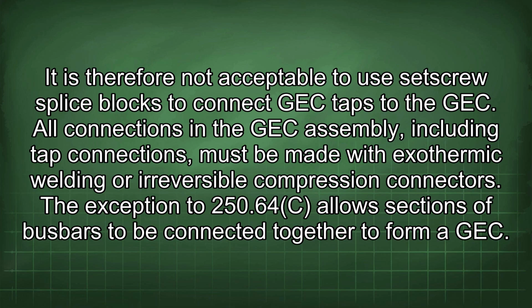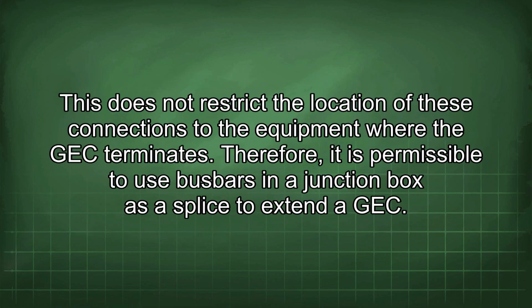All connections in the GEC assembly, including tap connections, must be made with exothermic welding or irreversible compression connectors. The exception to 250.64(C) allows sections of busbars to be connected together to form a GEC. This does not restrict the location of these connections to the equipment where the GEC terminates. Therefore, it is permissible to use busbars in a junction box as a splice to extend a GEC.